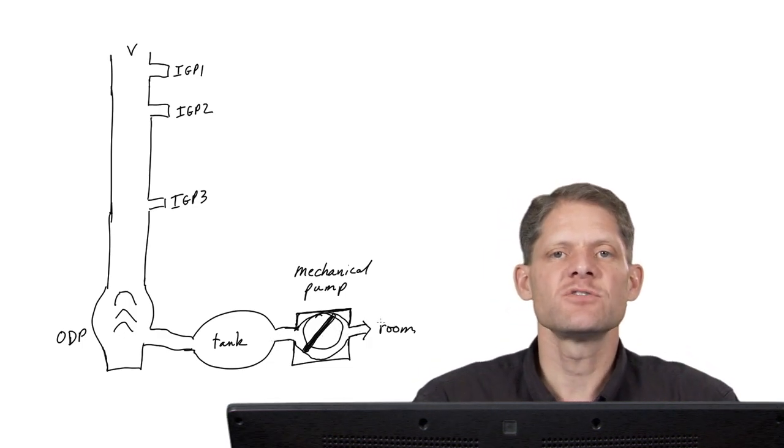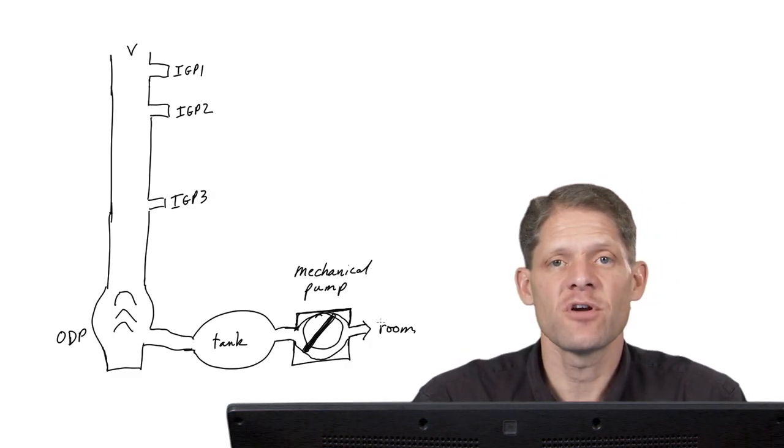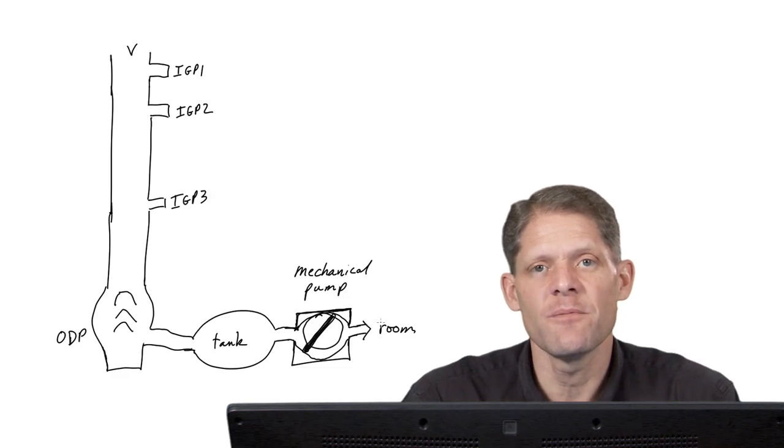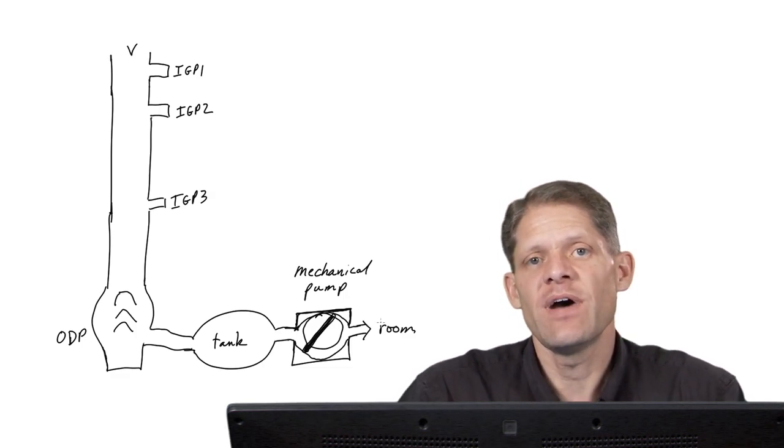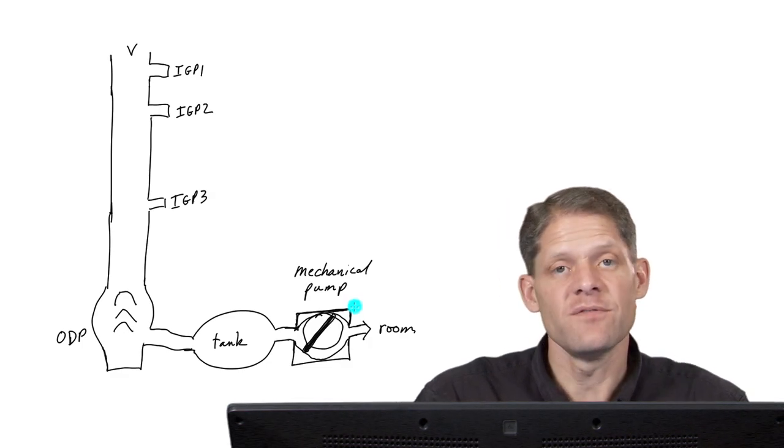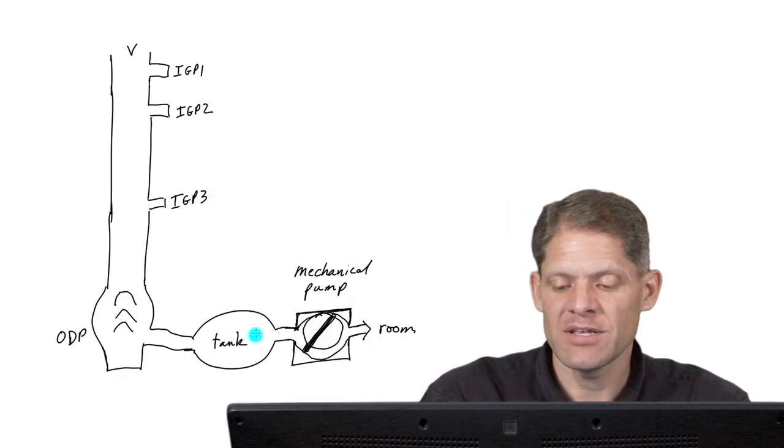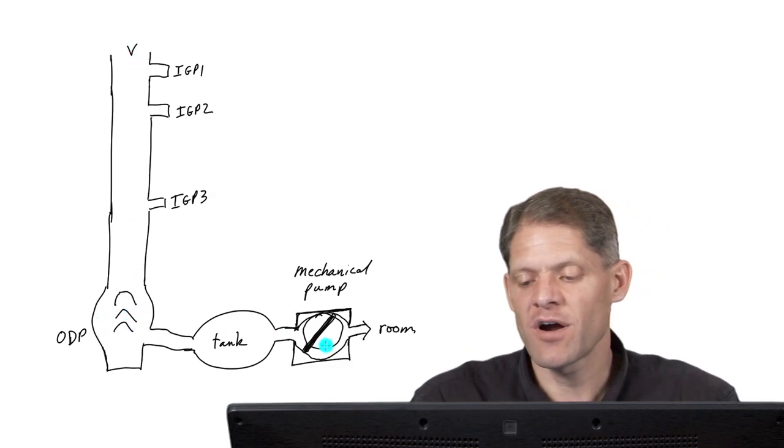When a microscope is vented, first of all, all the pumps are shut off and then valves are opened to allow atmospheric pressure to vent into the column. Once it's time to evacuate the column, the valves are sealed, obviously, and then first the mechanical pump is started, and it evacuates the tank, the oil diffusion pump, and the column as far as it can go.